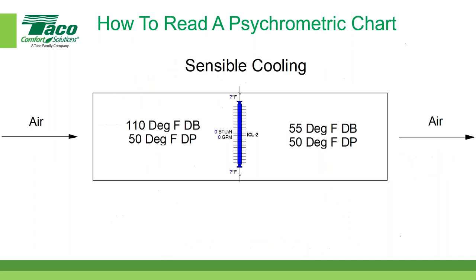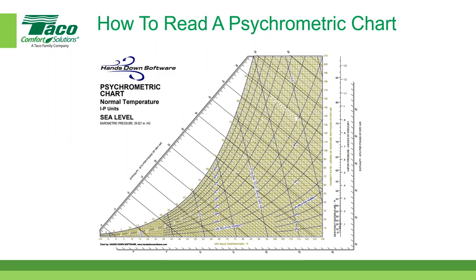The next one is actually just as easy. It's called sensible cooling. Now we're going the other way. In sensible cooling, we're starting off with 110 degrees Fahrenheit dry bulb. We're cooling the air down to 55 degrees Fahrenheit dry bulb at a constant dew point temperature. Once again, constant dew point temperature. So if you can try to remember these numbers, Brett, so I don't screw them up. I'm going to go over here to my psych chart. I'm going to start with, I think we said about 110 degrees. So here's 110, roughly right here. Yeah, there it is right there.